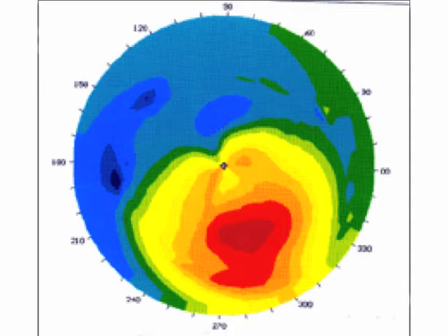And you can see that if you follow this cornea down to 290, that's to say in about the 5 o'clock position as we're looking at this cornea, it's very steep there. And if we go all the way up to 120, we see actually that the cornea is very flat there, and the keratometer is going to average those two out when it gives us the keratometric reading for the meridian of 120. It's not going to provide us with much insight about the curvature of this cornea.